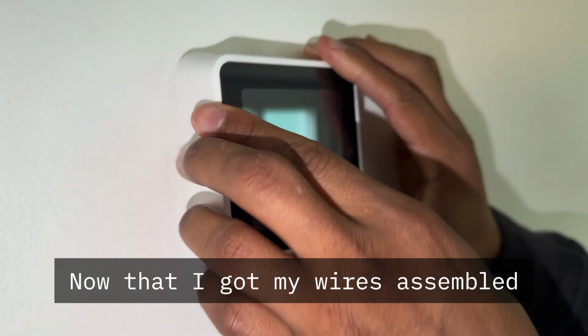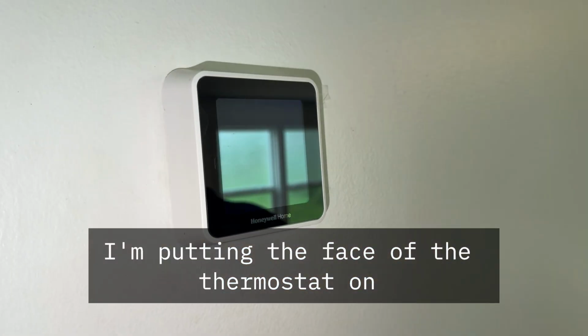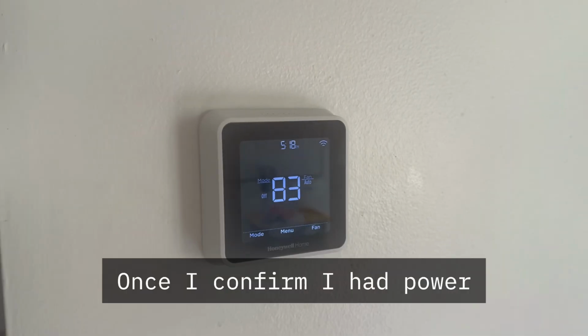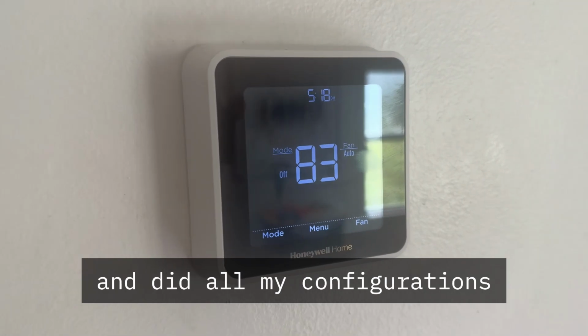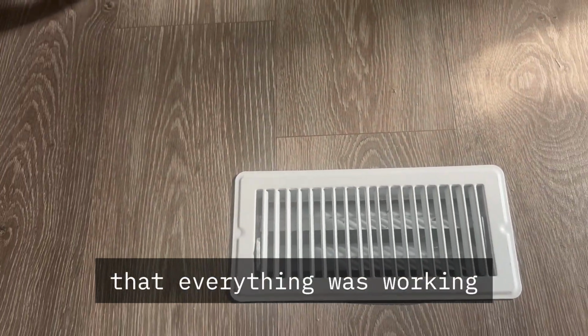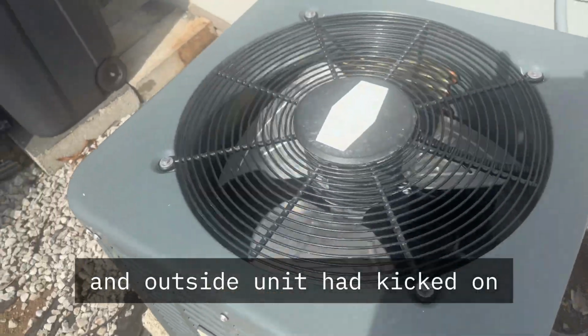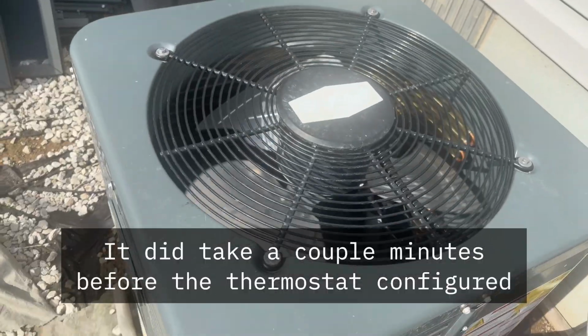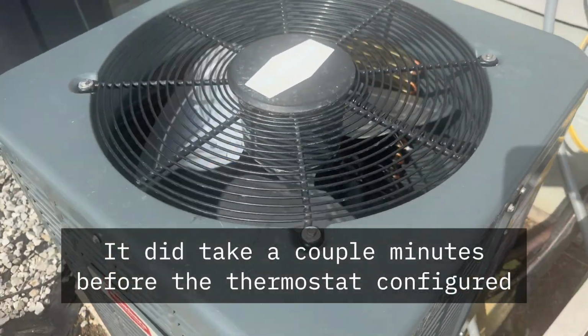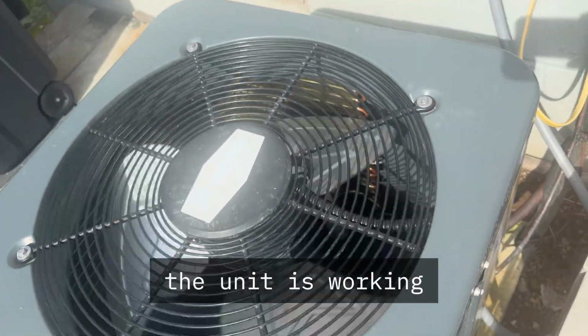Now that I've got my wires assembled, I'm putting the face of the thermostat on, waiting for everything to get powered up. Once I confirmed I had power and did all my configurations, I went to the vent to make sure that everything was working and the outside unit had kicked on. It did take a couple of minutes before the thermostat configured, but as you see, the unit is working.